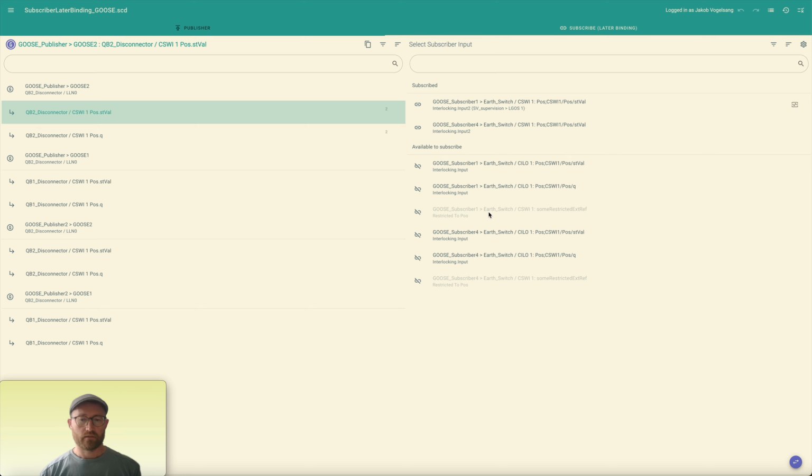In addition to that, such an external reference can restrict the data that it wants to accept through attributes pLN, pDO, pDA, and pServT. So pLN, pDO, pDA as a combination allow you to check for the common data class and the basic type that you want to restrict, and the pServT allows you to restrict the service type that you want to accept. So for example, in this case, a goose.